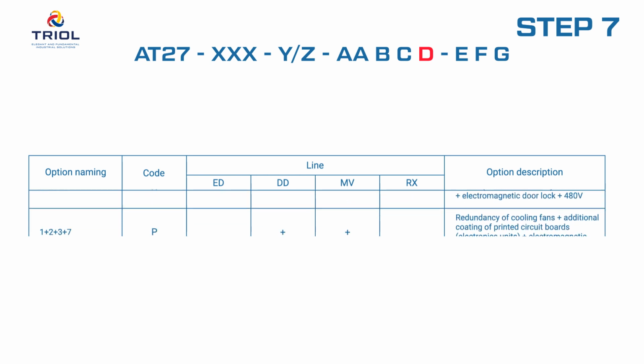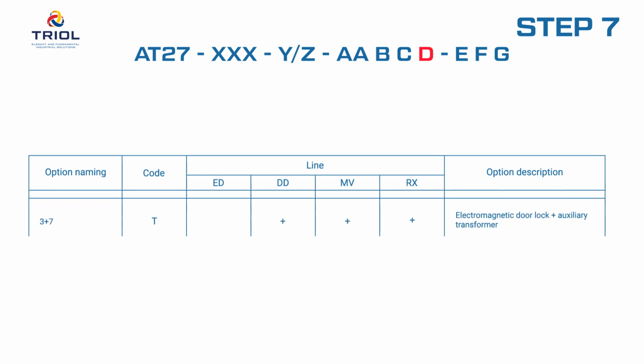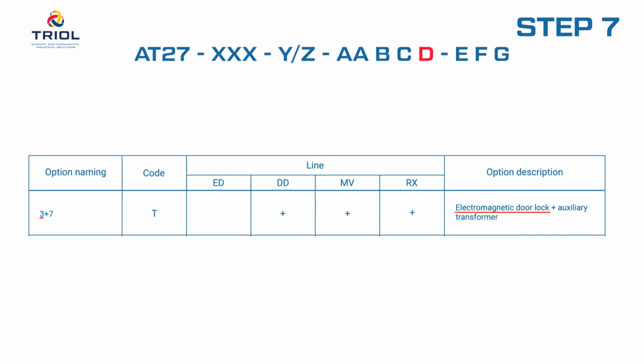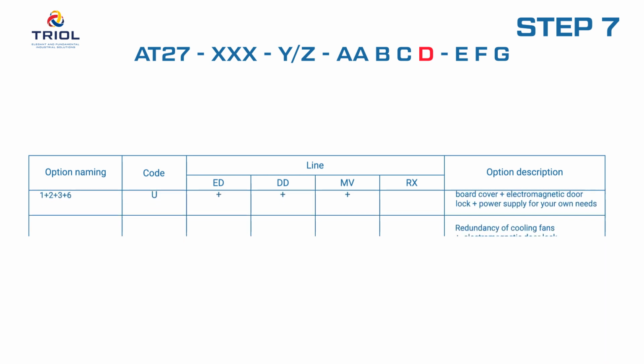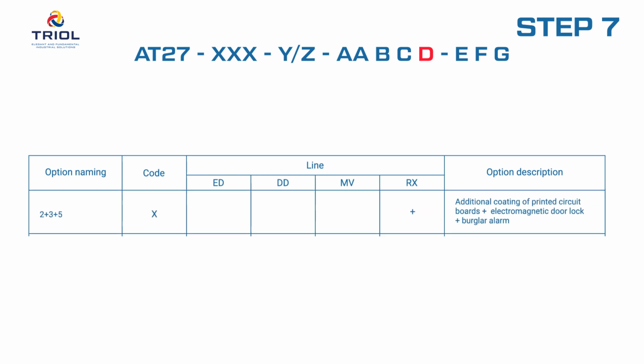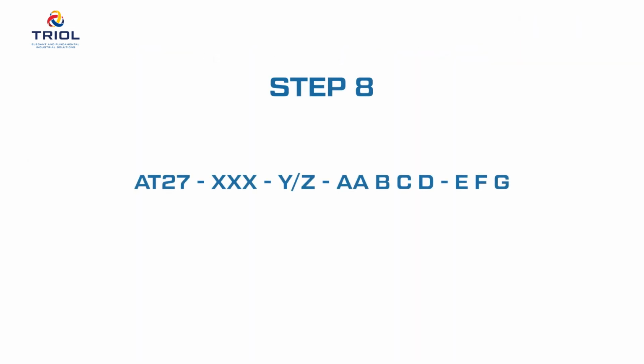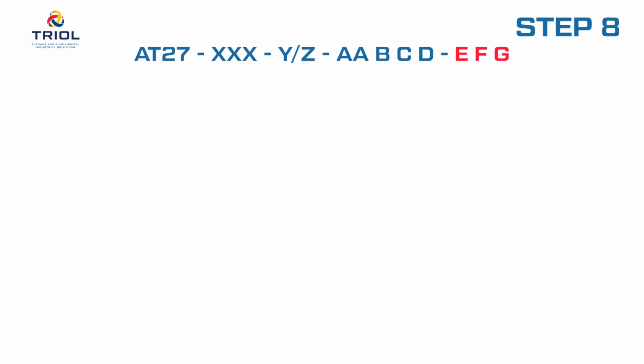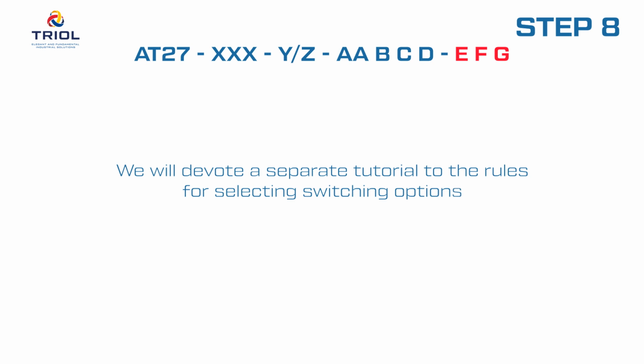For example, when ordering a VFD with a set of additional options, electromagnetic door lock, option designation 3, built-in auxiliary transformer, option designation 7. We get a combination of additional options. 3 plus 7 equals T. For the RX line block box design, 3 additional options are available related to the choice of power switching. The choice of power switching has its own characteristics. We will devote a separate tutorial to the rules for selecting switching options.